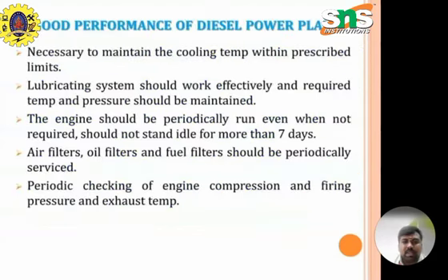For the good performance of diesel power plants, these are the necessary steps to be taken. It is necessary to maintain the cooling temperature within the prescribed limits. The lubricating system should work effectively and the required temperature and pressure should be maintained. The engine should be periodically run even when not required. It should not stand idle for more than 7 days. Air filters, oil filters and fuel filters should be periodically serviced. Periodic checking of the engine compression, firing pressures and the exhaust temperature should be done.